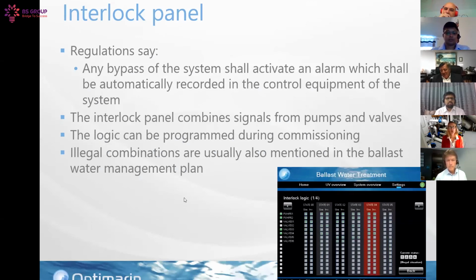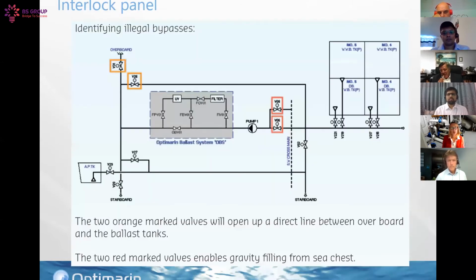The interlock panel can be used if you have a number of bypass possibilities and you don't have a fully automated system. For example, I think you can see it in the next slide. If you have an illegal bypass, the rules say that if you have any bypass of the system, you need to log it and you need to alarm it, because it's not allowed to bypass the system. For example, if you have these two valves open, then your system can just fill like this by gravity, or you can discharge like this, or the other way around. So you want these alarmed, and if these are not automated, you can use the interlock panel to connect those signals and program the logic: if this valve plus this valve is open, then it should give an alarm.